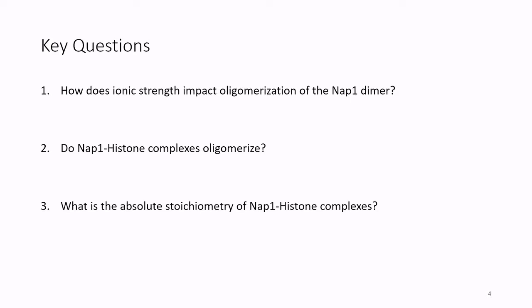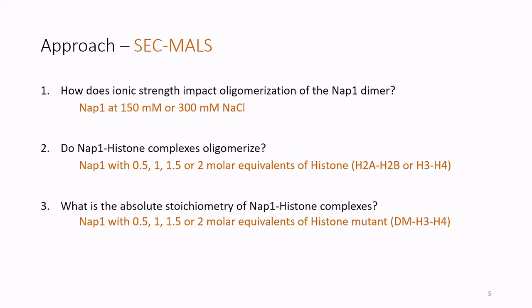All of our questions can be answered using a technique called SecMALS. SecMALS is size exclusion chromatography coupled to multi-angle light scattering. It is composed of two major components: the SEC part and the MALS component. The SEC component is comprised of an HPLC pump that drives our proteins and buffer to the SEC column. The size exclusion column then separates our proteins based on shape and size, and enters a UV detector where we obtain a chromatogram based on the protein's absorbance, giving us peak height, peak shape, and elution volume.